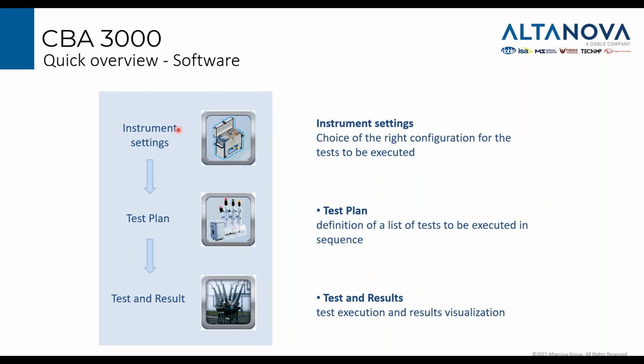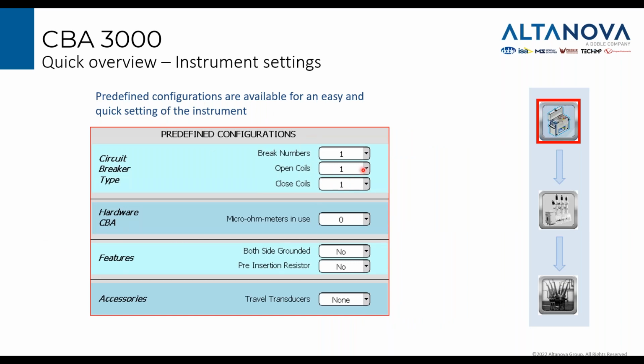gives the possibility to perform the test in 3 steps. The first is to choose the right configuration of the instrument, because CBA 3000 is a programmable device. So before performing the test, you have to tell it the configuration of the breaker you are going to test. Then you decide a test plan of operations, and in the end you get your results. This is an example of the configuration you have to indicate in the beginning. You have to tell the number of breaks per phase, the number of open and close coils, if you want to use micro-ohm-meters, if the circuit breaker is grounded on both sides, yes or no, and so on.